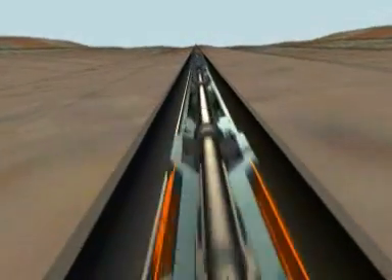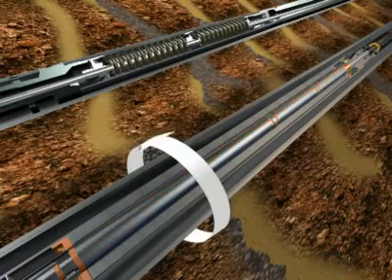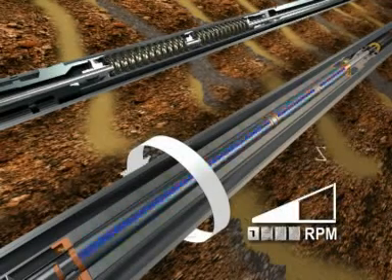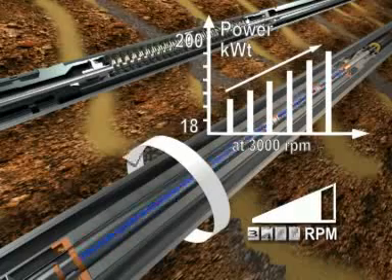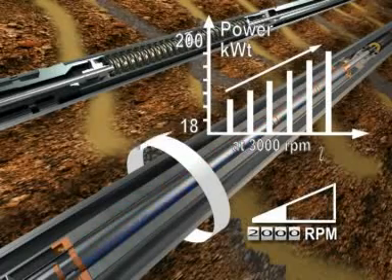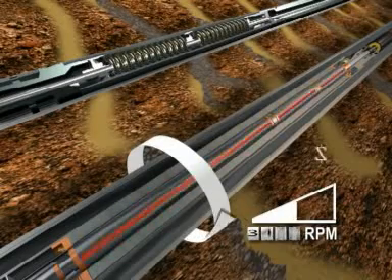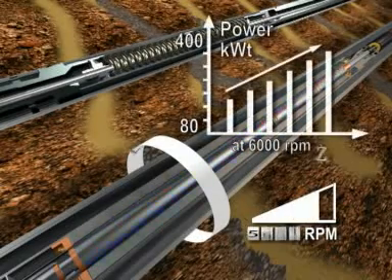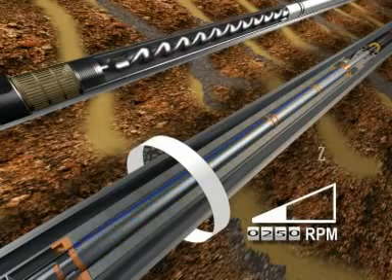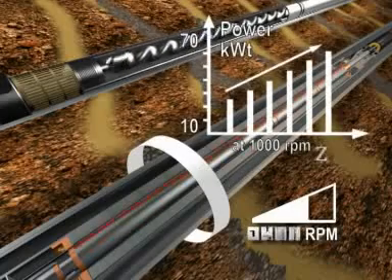Component one: the electrical motor for submersible centrifugal or progressive cavity pumps. Centrifugal pumps with motor speed ranges from 500 to 3,500 RPM, with power ranges from 18 to 200 kilowatts at 3,000 RPM; and from 2,000 to 6,000 RPM, with power ranges from 80 to 400 kilowatts at 6,000 RPM. PCP with speed range from 250 to 2,000 RPM, with power range from 10 to 70 kilowatts at 1,000 RPM.